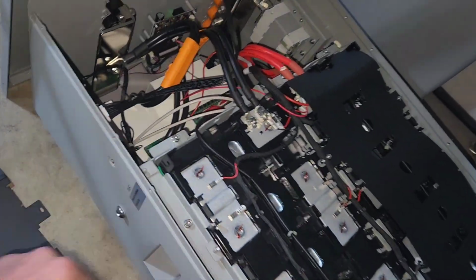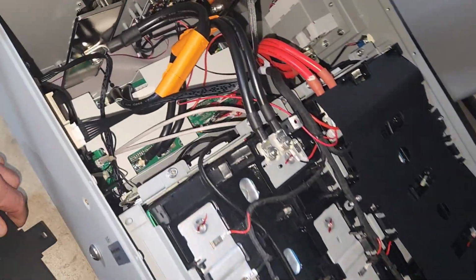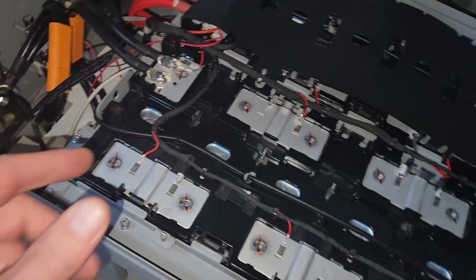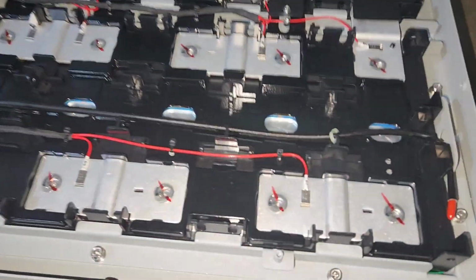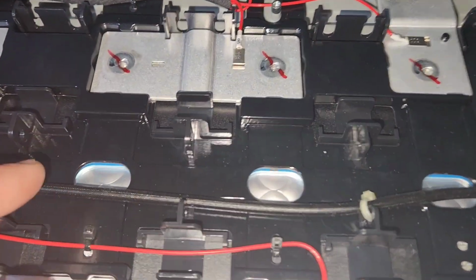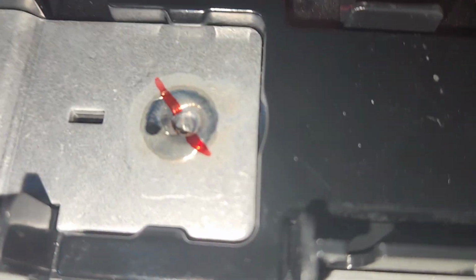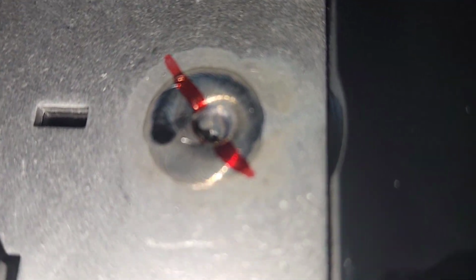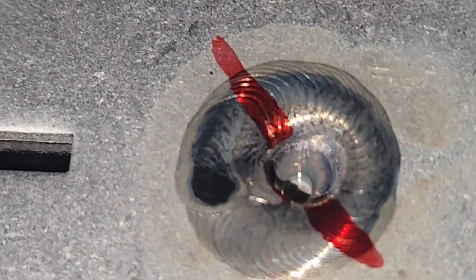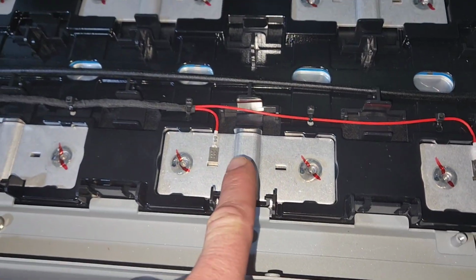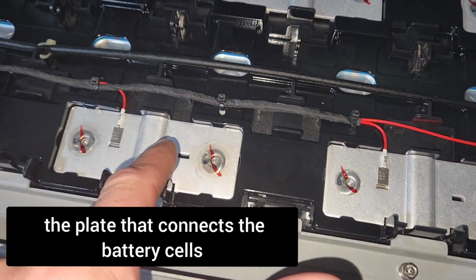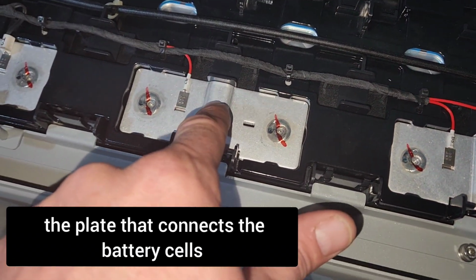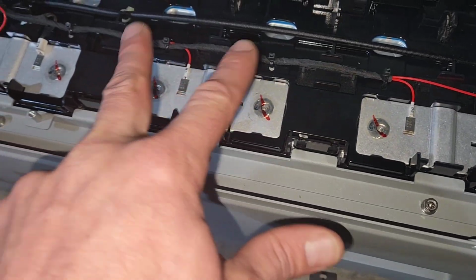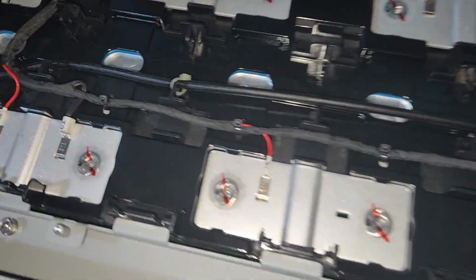So I dove in here a little bit more, just took this cover off. Yeah, those are definitely the fire arresters. And look at this, these are not just spot welded, those are like, that is a serious weld. So these jumpers are not coming off. And it looks like there's a little bridge in between each connection, so it can expand and contract a little bit.